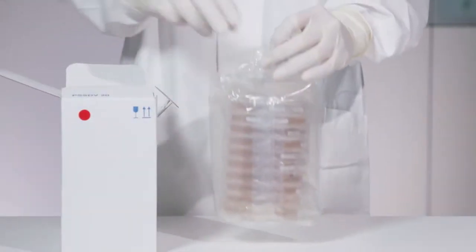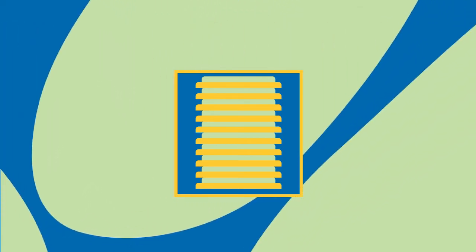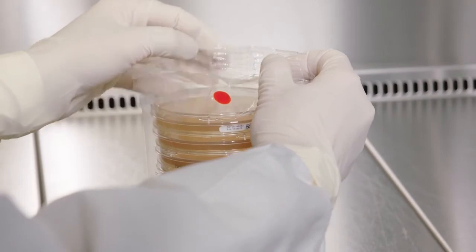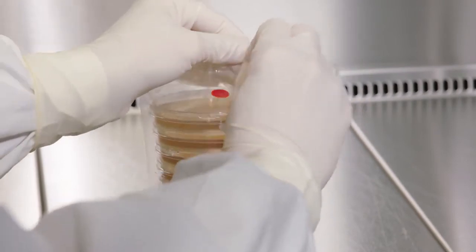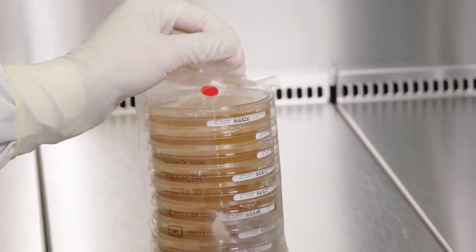Triple bagged ICR Plus contact and settle plates allow a safe and sterile transfer into clean rooms by removing one bag per material lock. For use in isolators, the innermost bag can be hung up during decontamination by using the hole.